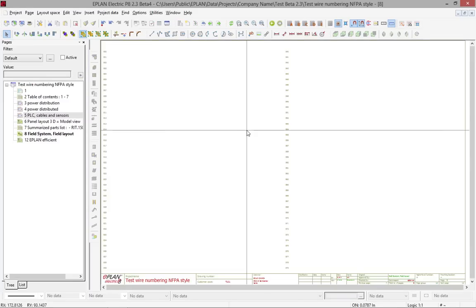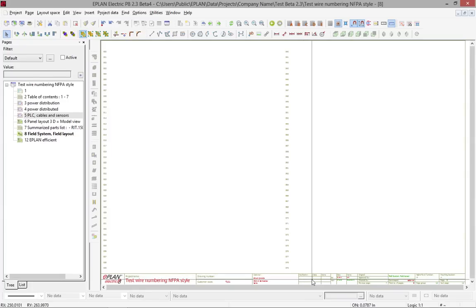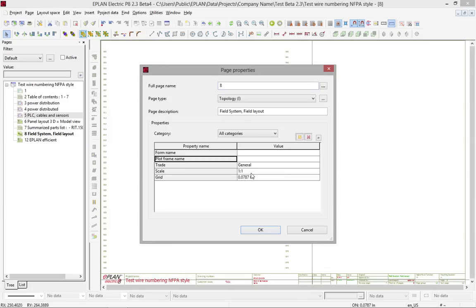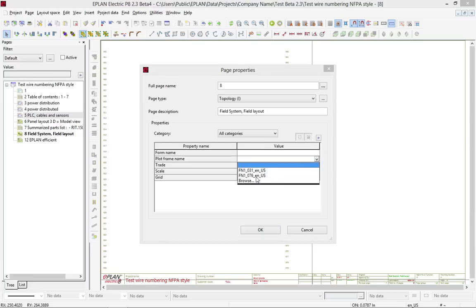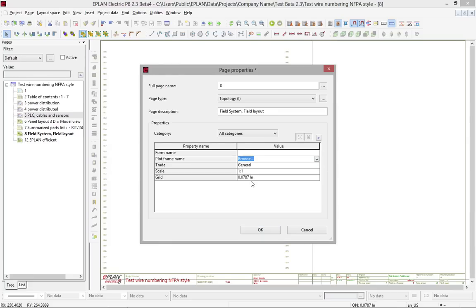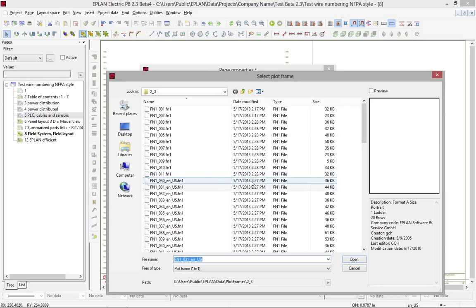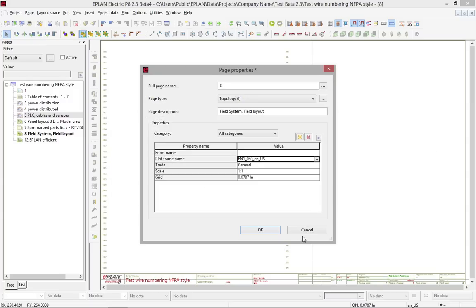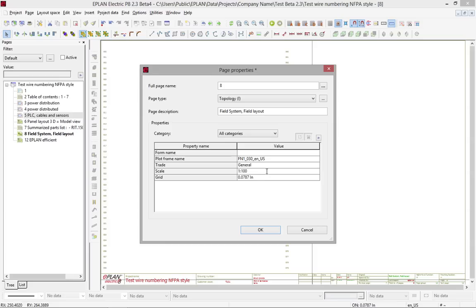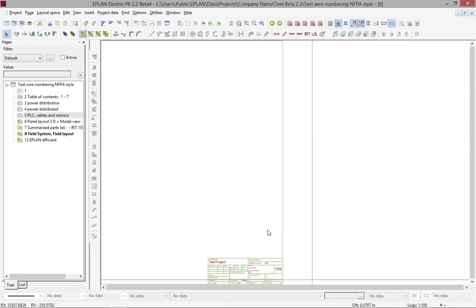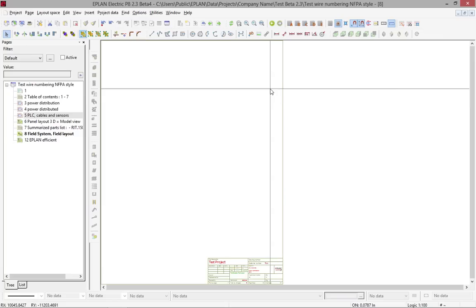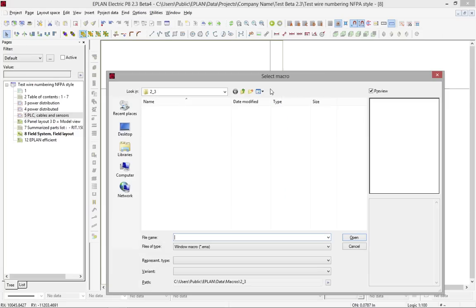It's a field overview or field layout of your cable trays and all your sensors or motors and whatever is placed out there. Typically when you draw this, you like to draw it in a one-to-one scale. So what's important here is to pick a plot frame that matches the size of your paper. If you have A-size paper, I recommend you choose an A-size paper. You can imagine if you print on A-size, you will have to apply a scale of 1 to 100 or 1 to 200 to fit a complete plant.